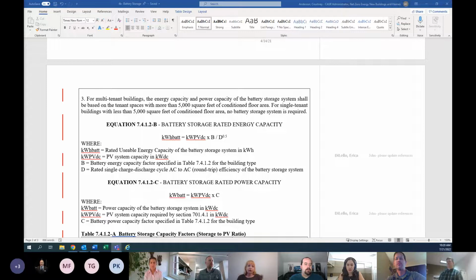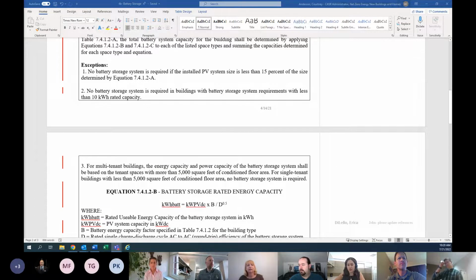So when I go to exception 1, though, it says no battery storage system is required if the installed PV system size is less than 0.25 kW DC capacity per square foot of conditioned floor area. So if I have a 6,000 square foot commercial building, single tenant, it could be a restaurant or retail space. Under exception 3, it would automatically be required the way it's written, since it is 5,000 and above. But if you go to 1, a battery system would not be required for 6,000 square feet unless it has a PV system of 1.5 megawatts, which is huge.